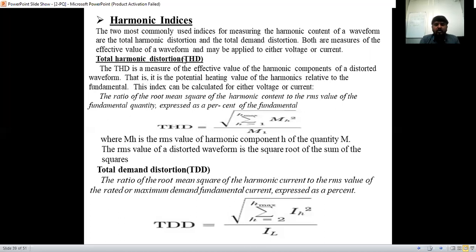See, this THD is total harmonic distortion. It is the ratio of the RMS value of the harmonic content, not current, to the fundamental quantity. But the demand distortion is considered based on the current only. It is the ratio of the RMS value of the harmonic current to the maximum current or rated current. This H indicates harmonic, and L indicates the rated load or maximum demand. So we take the square root of the summation of I1 to IH. For harmonics, we use greater than one, or directly we can start from 2. Here we have used greater than 1.